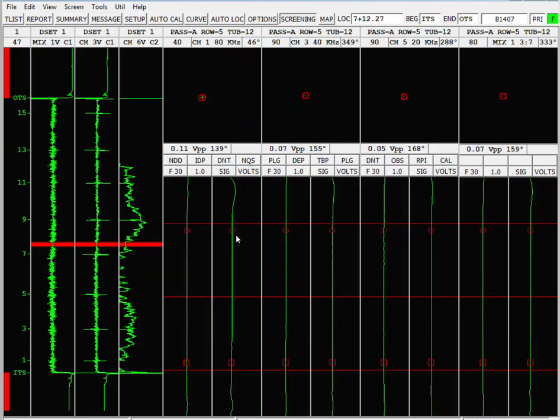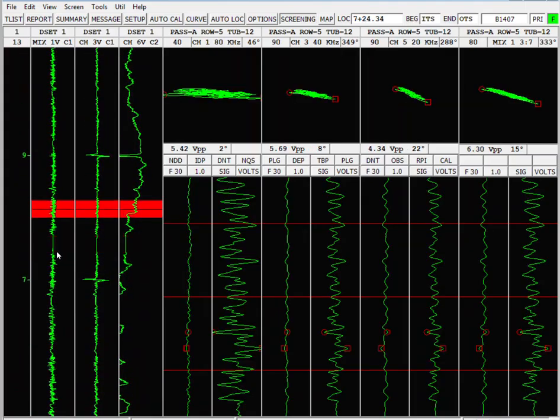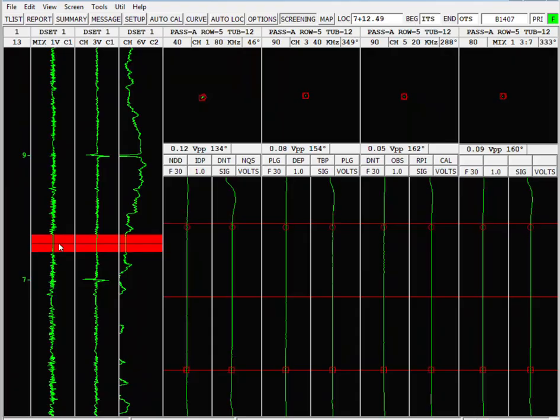Now, if you stop pulling the data and you're right on the edge of a discontinuity, then you start pulling the probe back, you could easily miss a discontinuity in your tube that could eventually lead to a tube leak, and nobody wants that. It's even more evident if I take the middle scroll wheel on my mouse and just expand the strip charts. Now look at how evident that is. It's just a dead spot. This tube was rejected as bad data because of probe motion stopping.